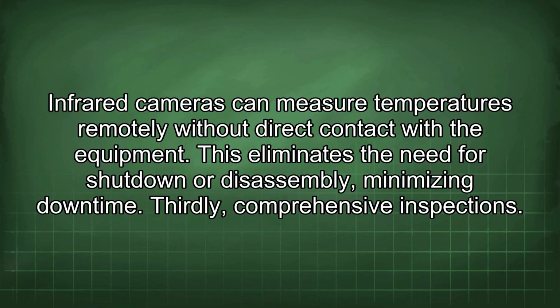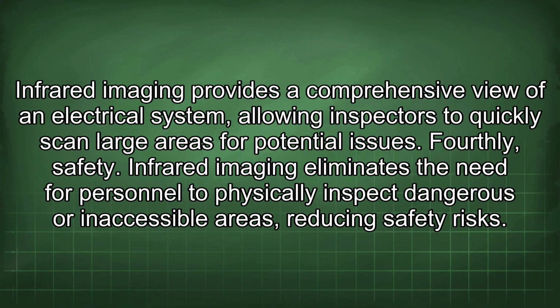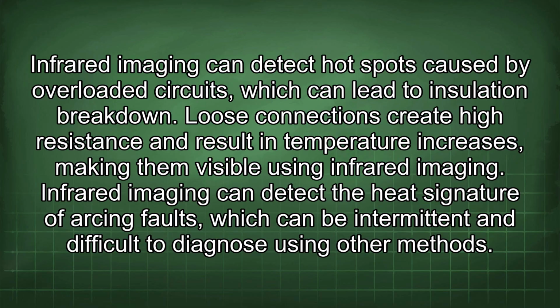Thirdly, comprehensive inspections. Infrared imaging provides a comprehensive view of an electrical system, allowing inspectors to quickly scan large areas for potential issues. Fourthly, safety. Infrared imaging eliminates the need for personnel to physically inspect dangerous or inaccessible areas, reducing safety risks. Infrared imaging can detect hotspots caused by overloaded circuits, which can lead to insulation breakdown.